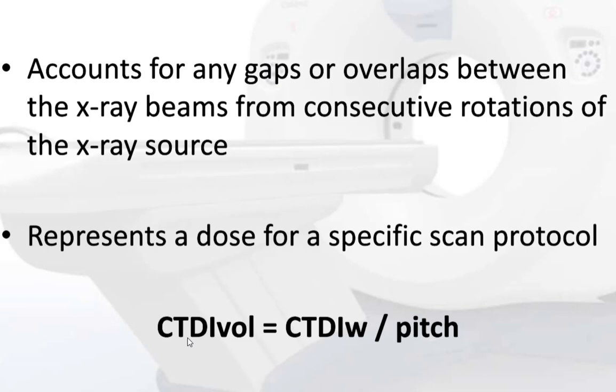CTDI volume accounts for any gaps or overlaps between X-ray beams from consecutive rotations of the X-ray source. It represents the dose for a specific scan protocol. The formula for CTDI volume is CTDI-W (weighted) divided by pitch.